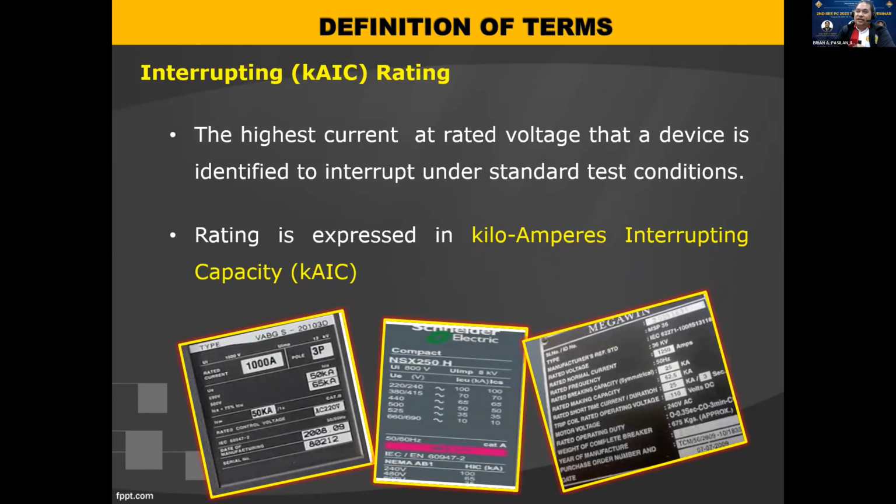That a circuit breaker or a fuse can interrupt safely, no, during short circuit or ground fault, meaning to say at those conditions, malalaking current na yan in terms of 1,000 amperes, hindi yan masisira, no, pag mag-interrupt siya. The problem now, if undersize yung kAIC rating mo, ang mangyayari yan pag during interruption, pwede yang ikasisira o talagang sasabog yung circuit breaker natin kung grabe yung pagka-undersize ng kAIC rating. So dapat talaga i-address. But this is not part of our topic.